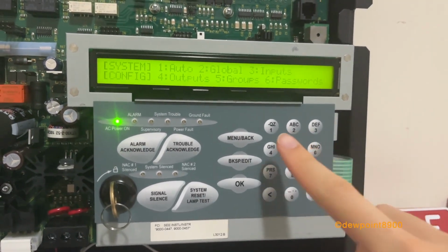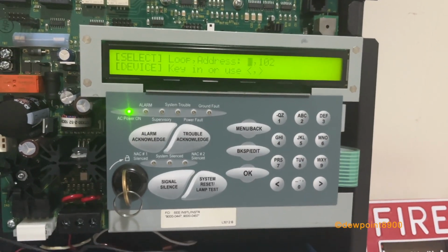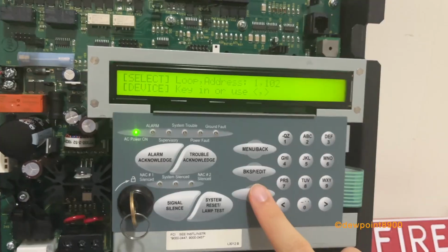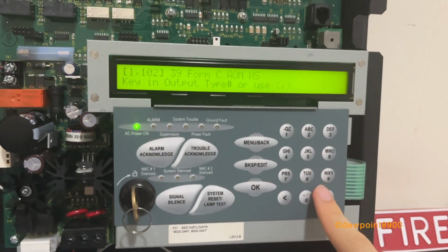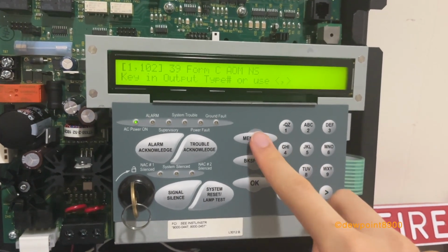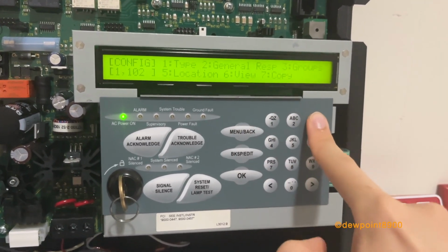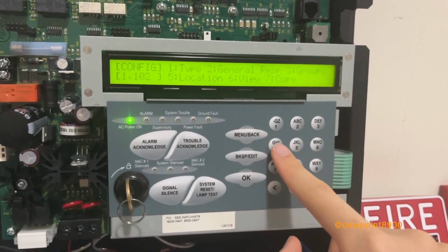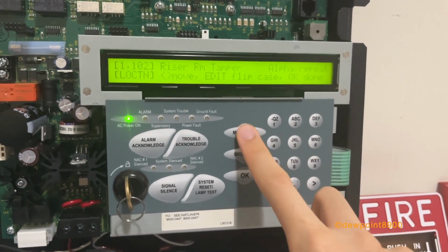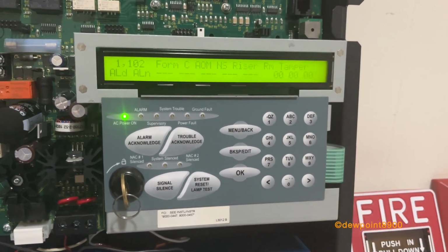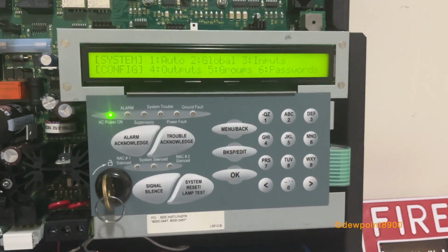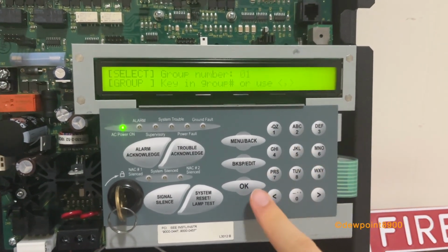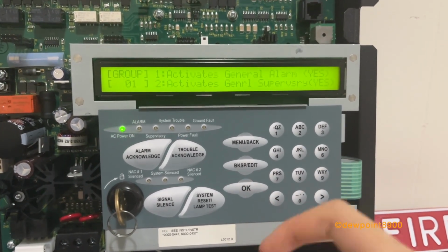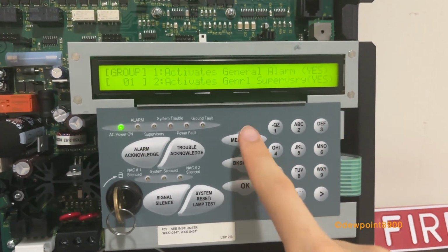Now let's look at outputs. Enter device address. 102 is the relay module down here. Type, it's a Form C relay. General response options, groups, there's no group for this one. And pretty much everything else is the same. You got your location and your general summary of the device. Next is groups. We'll check group one, set whether to activate for general alarm and general supervisory.